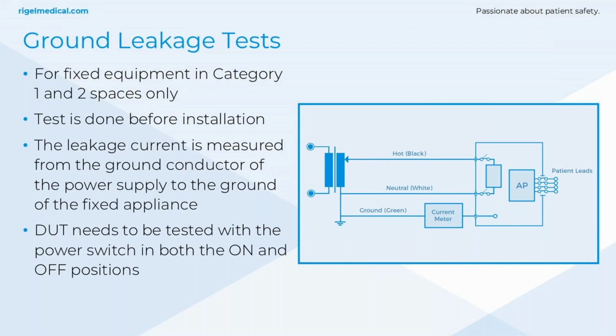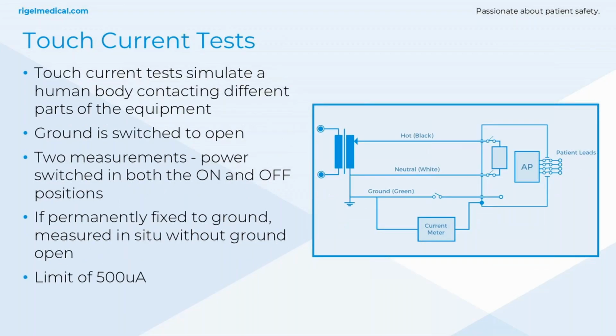And the SafeTest 60 plus does have a default of 10,000 microamps if set to NFPA 99. You can change that value if you want to, but I'll show you on the next slide when you move over to ground leakage that it is set to 10,000 microamps. So I'll talk a little bit about touch current tests or chassis leakage current tests before we go on to the demo, and then I'll show you how ground leakage and touch current tests are done with the SafeTest 60 plus.